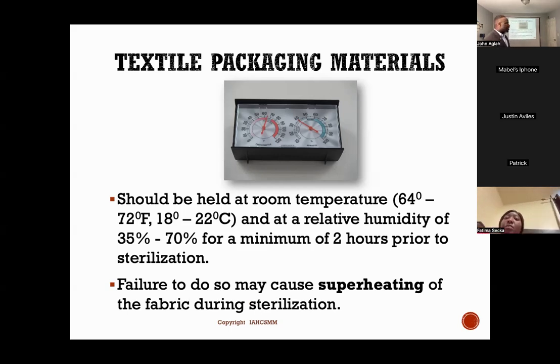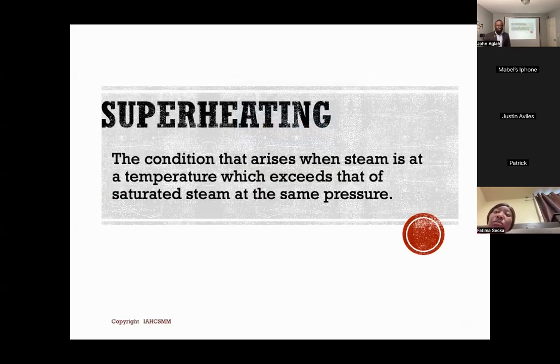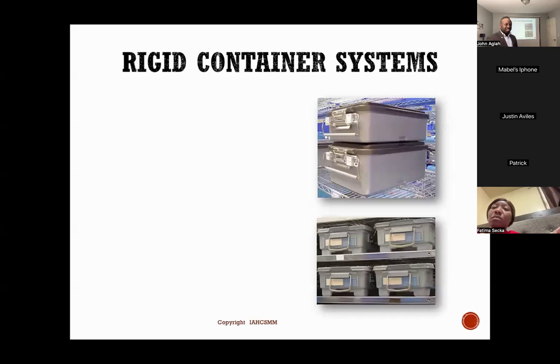Failure to do so will cause what we call superheating of the fabric during sterilization. If the textiles are not at the right temperature, it's going to cause superheating. Now, what is superheating? A good definition to know: the condition that arises when steam is at a temperature which exceeds that of saturated steam at the same pressure. Okay. Rigid container system.